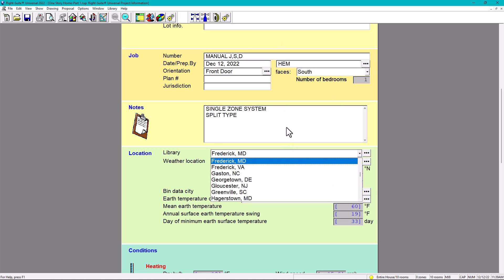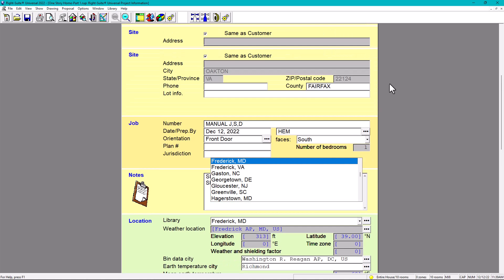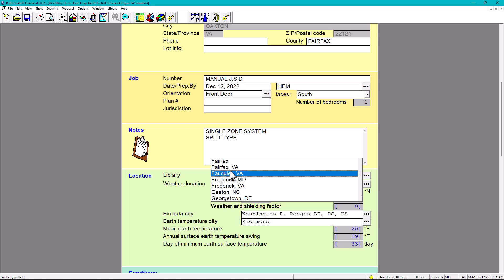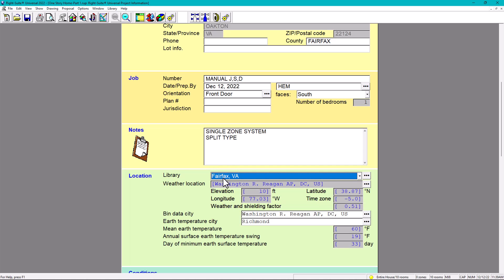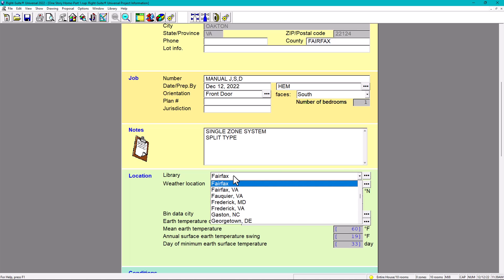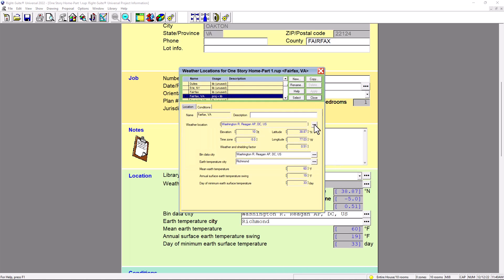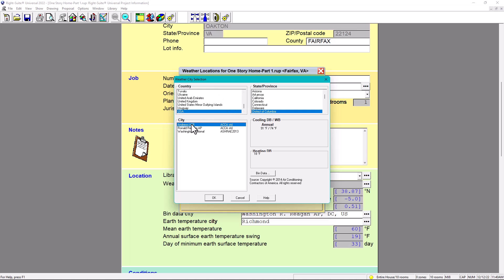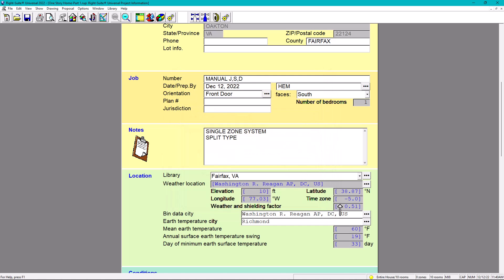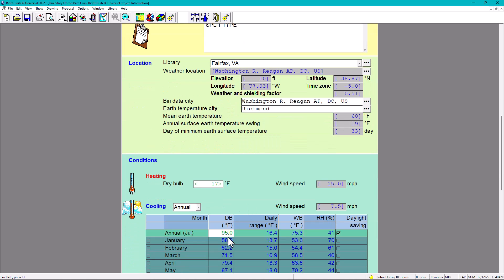Most importantly, you need to choose your weather location. This is based on the county — this project is located in Fairfax County, so we're going to select Fairfax, Virginia County. If you want to make changes to your weather location, you can go in here and change all the details based on your climate weather station. You can see the design temperatures, and you can press F8 to restore defaults.